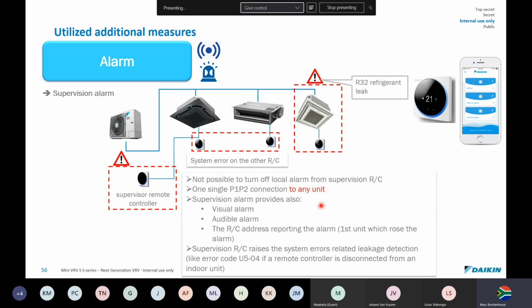That won't work. So you'll have one single P1, P2 connection to any unit, which I've mentioned already. The supervisor's alarm will provide a visual alarm, an audible alarm, and it'll also say the remote control address on which alarm is going off. For the supervisor's alarm, you can also hook it into any one of these P1, P2s, whichever is closest to the supervisor's room.